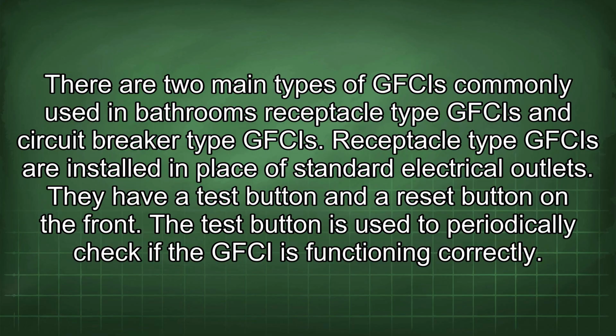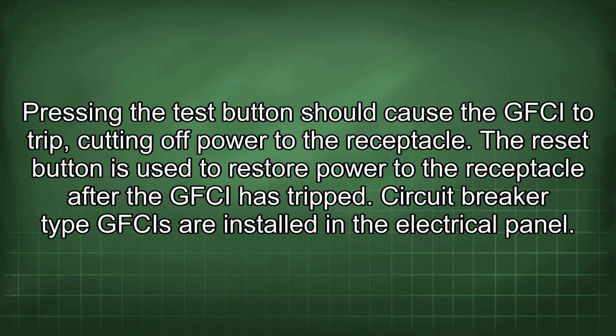GFCIs. Receptacle-type GFCIs are installed in place of standard electrical outlets. They have a test button and a reset button on the front. The test button is used to periodically check if the GFCI is functioning correctly. Pressing the test button should cause the GFCI to trip, cutting off power to the receptacle. The reset button is used to restore power to the receptacle after the GFCI has tripped.